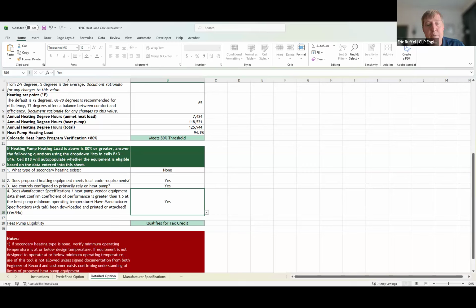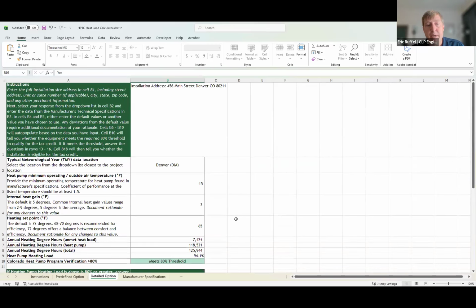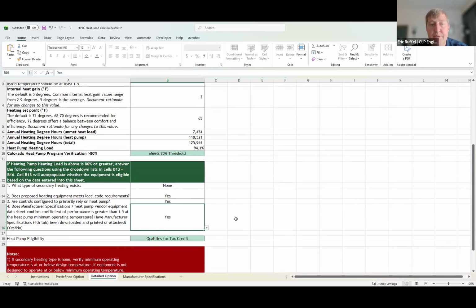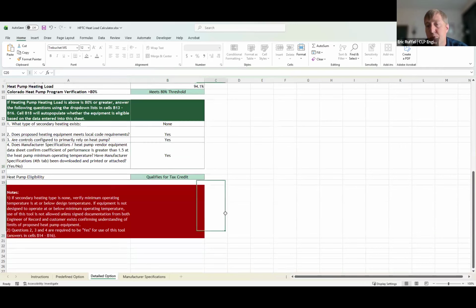So it's important when using either of these tabs that local codes and requirements are met. If a heat pump is proposed that likely will not be able to provide sufficient heat to meet design condition minimum temperatures, then all parties should be aware of those limitations, including the customer and the permitting authority. The reason we state that, in particular what's in red under note 1 below, is that it's possible to meet the 80% threshold, but for the heat pump to struggle to maintain a certain temperature on the coldest days in Colorado. So if the heat pump doesn't have supplemental heating, and if it's going to struggle, then the parties should know. But that concludes the demonstration on use of the tool.